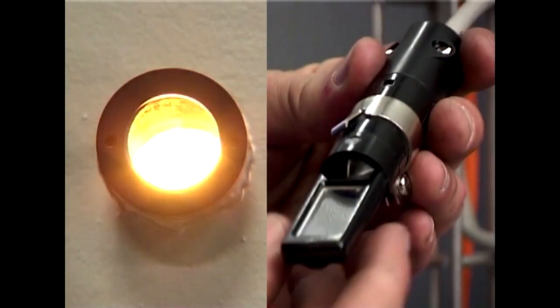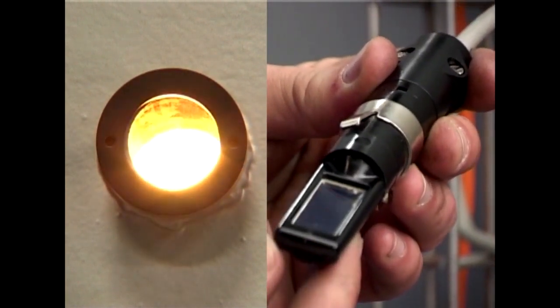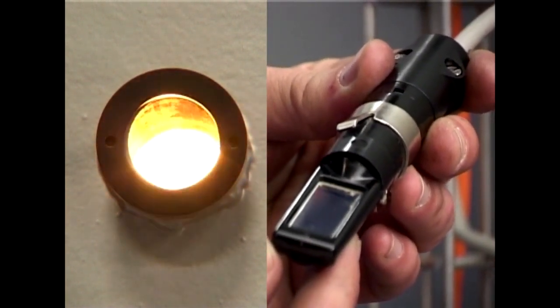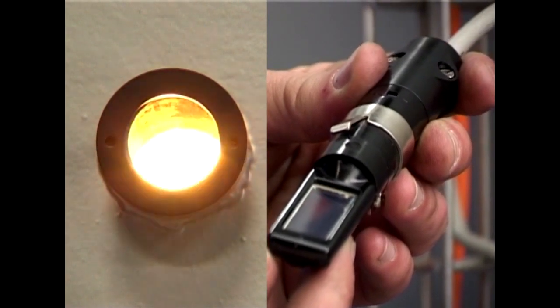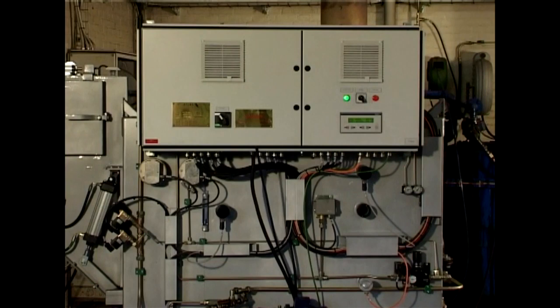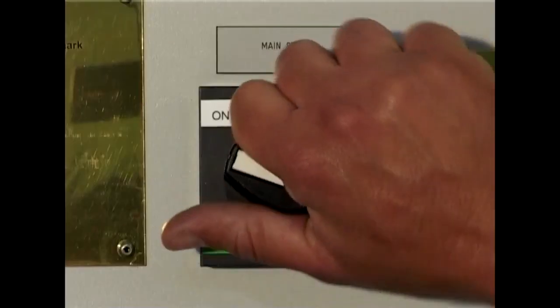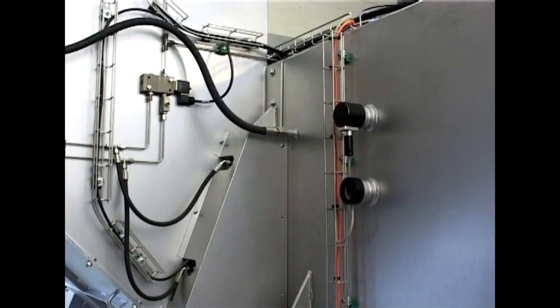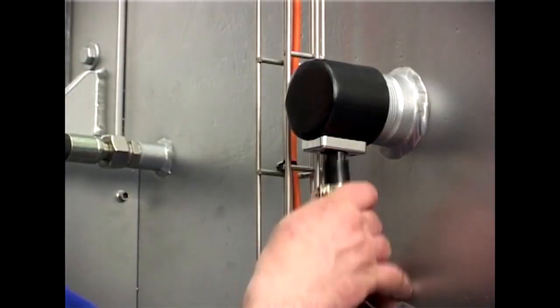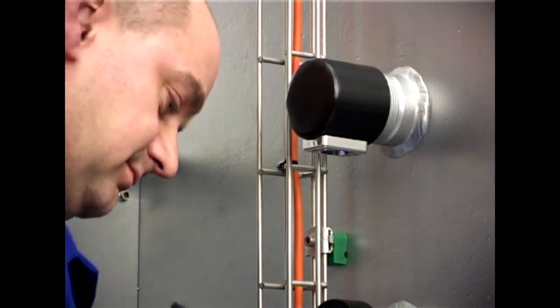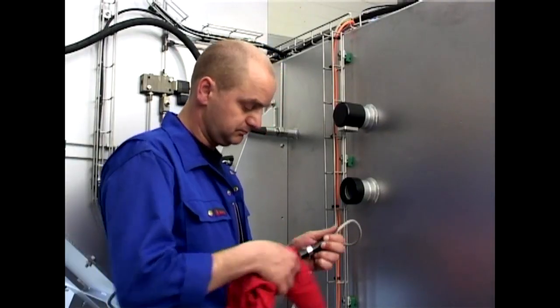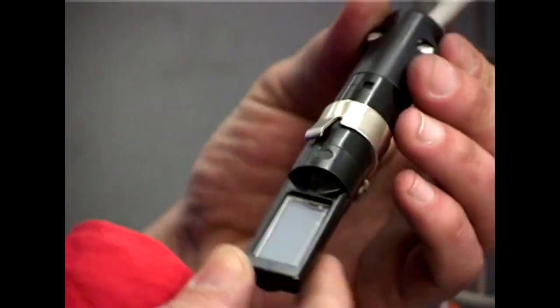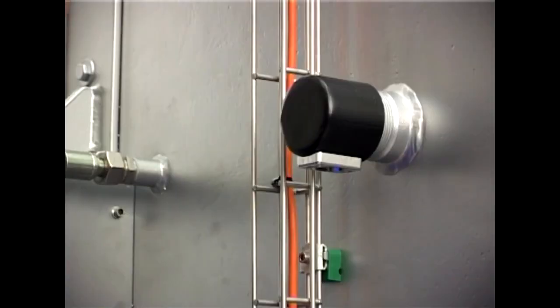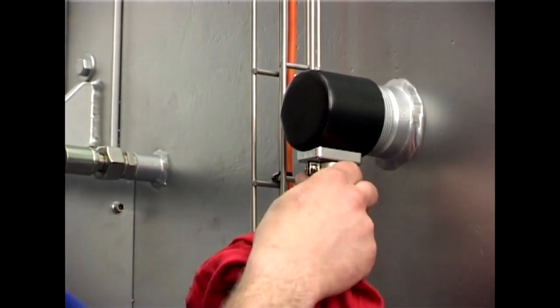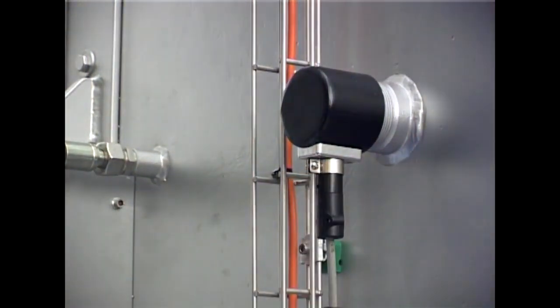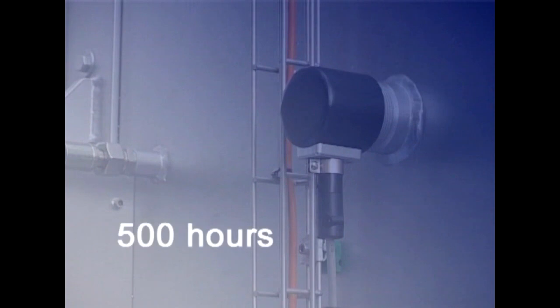Flame detectors are wear items and have only a limited lifetime, as they are directly exposed to the strong radiation heating and sooting from the combustion chambers. To service and to check the condition of the detectors, you should carry out the following procedure. Begin by switching off the incinerator. Then remove the flame detectors one by one on the burners and clean them for soot with a soft cloth. Inspect them for any damages like cracks or melting. Finally, reinstall the flame detectors. This routine should be carried out for every 500 hours of operation.